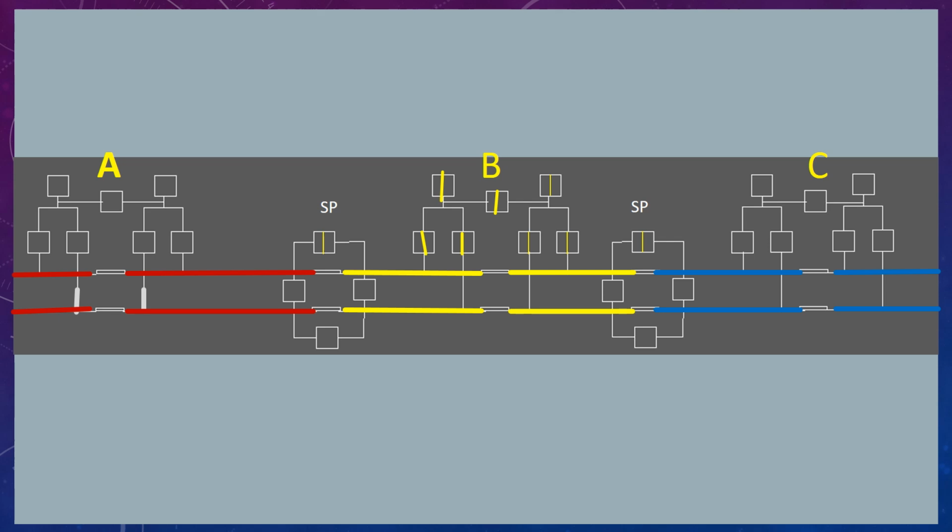Capacitor banks are also of two types. One is switching capacitors and another is shunt capacitor bank. For switching capacitors, when the load is more, a number of capacitor units will be inserted in the circuit, and when the load is less, they will be disconnected automatically. This system is automatic. But for shunt capacitor bank, the capacitor is fixed, and if there is low load or no load, then the power factor may become leading. At that time also it will reduce. I will show you all these things, how. Let's see.